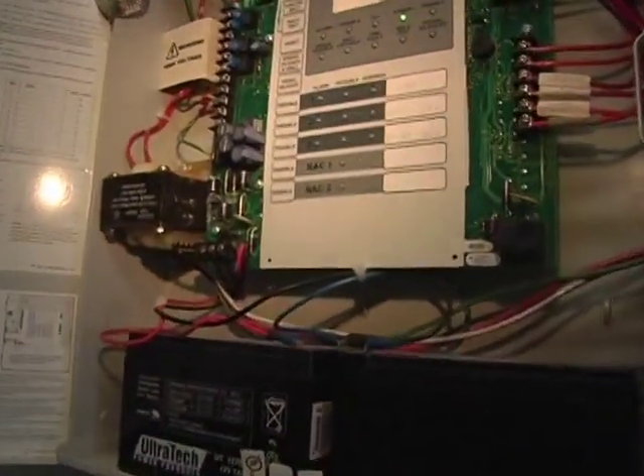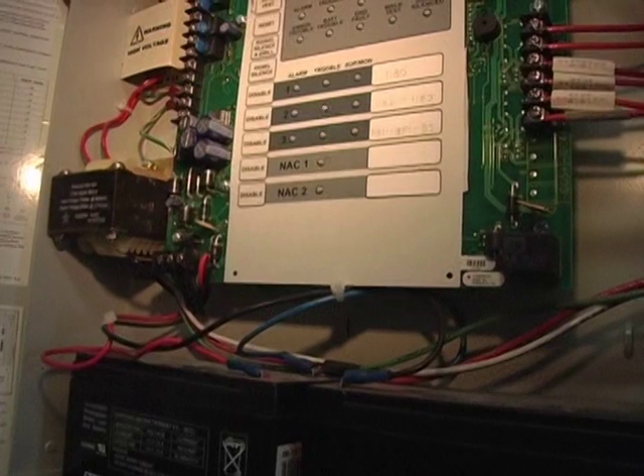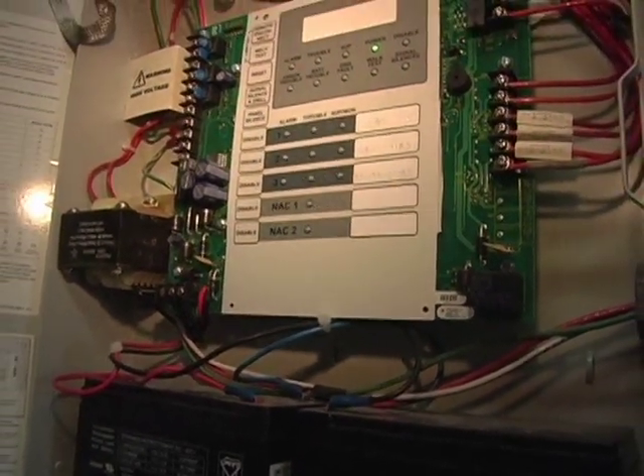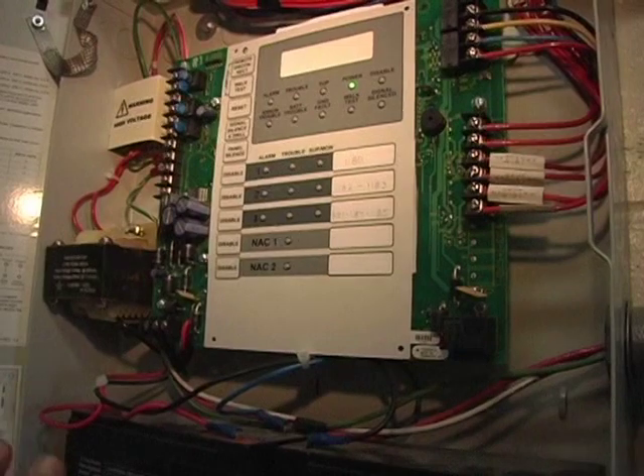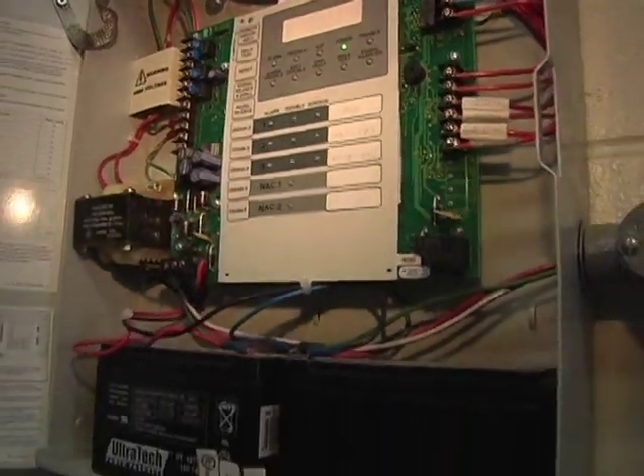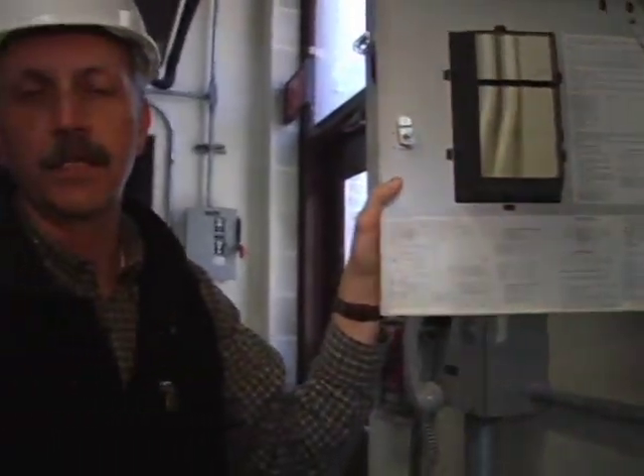We do have the capability of using the disable buttons to disable a particular circuit, depending on which sensor has gone into alarm. Here you will not get an indication as to which sensor is in alarm. That would have to be viewed through SCADA. There's a constant feedback to the SCADA system, giving you the level of each one of the detectors. So by going to the SCADA screen, you can determine which one is in alarm, and at that point work by disabling the circuit if you need to shut it down.